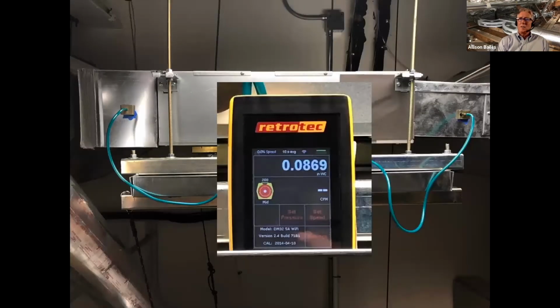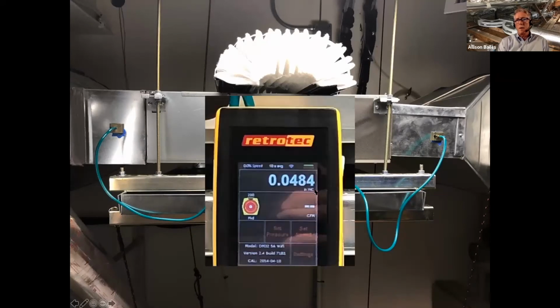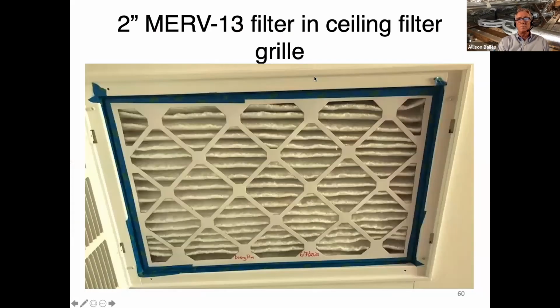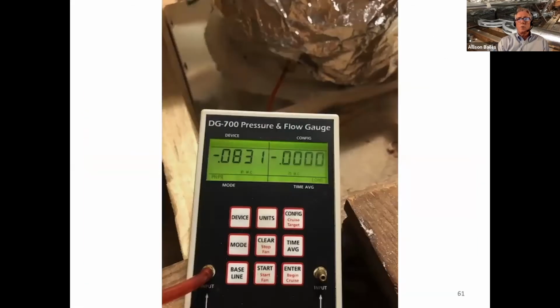But that's not true. This system at our office, 0.09 inch of water column static pressure, that's with a MERV 13 filter. When I took the filter out, you can see it's at about 0.05. So about 0.04 of the pressure drop was for the filter. 0.04 across the MERV 13 filter. That's pretty darn good. This is my house. We got ceiling grills here. They're 2 inches deep. The one at the office is 4 inches deep, and works great.